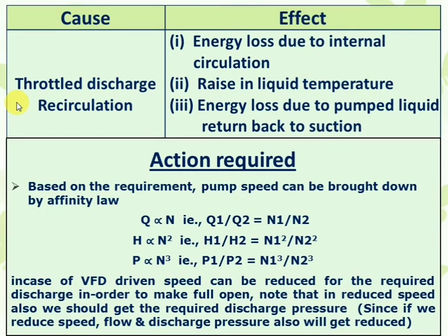So we should not throttle the discharge. Alternatively, we put a spill-back or recirculation line back to suction. But this also causes energy loss — the liquid we are pumping is returned back to suction, causing energy loss due to internal circulation, and rising temperature can also occur. So energy loss will be happening.